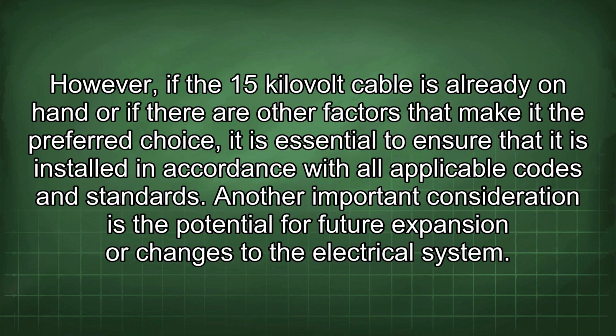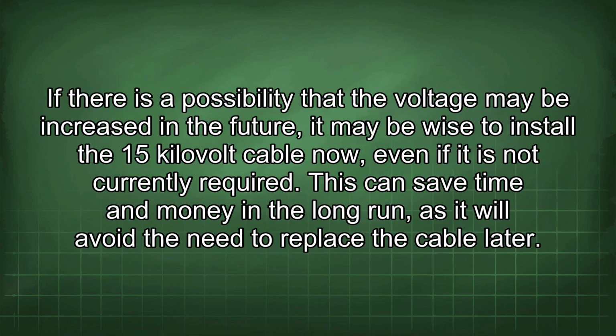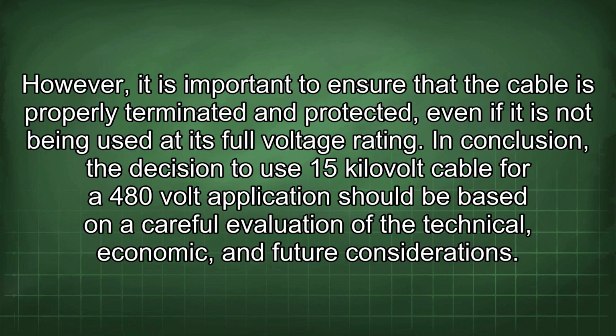Another important consideration is the potential for future expansion or changes to the electrical system. If there is a possibility that the voltage may be increased in the future, it may be wise to install the 15 kV cable now, even if it is not currently required. This can save time and money in the long run, as it will avoid the need to replace the cable later. However, it is important to ensure that the cable is properly terminated and protected, even if it is not being used at its full voltage rating.